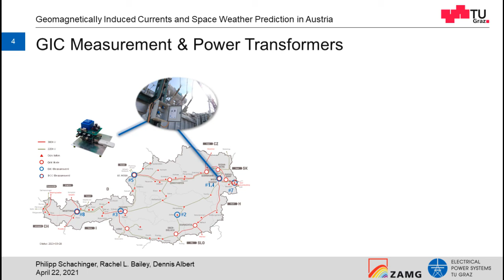On the left-hand side of the slide you can see the measurement electronic, which is accessible from remote via UMTS. In addition to the measurements on-site, we perform power transformer laboratory tests. We have modified 250 kVA power transformers in a way that the low voltage vector group can be changed from outside. This helps us to superimpose DC or low frequency currents on either side of the power transformer.